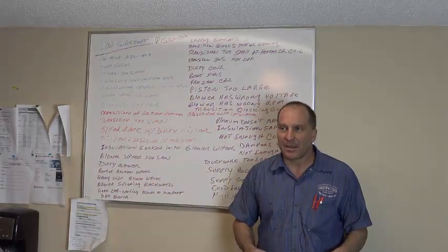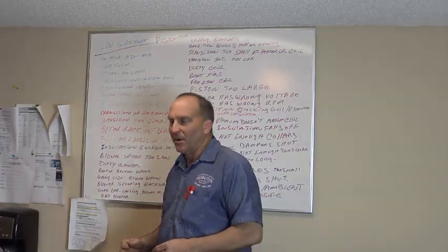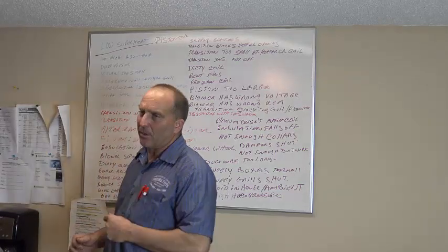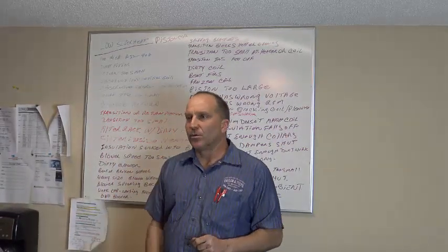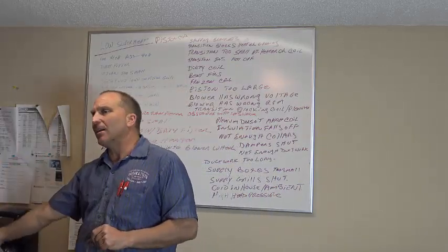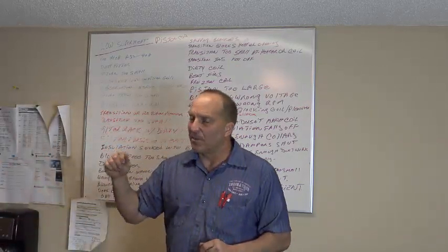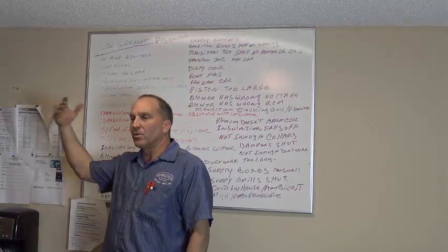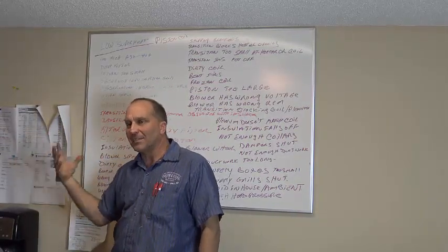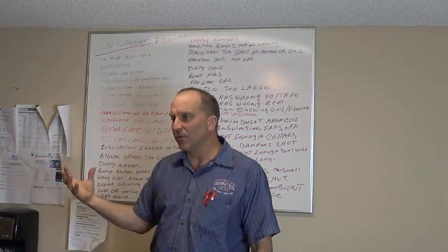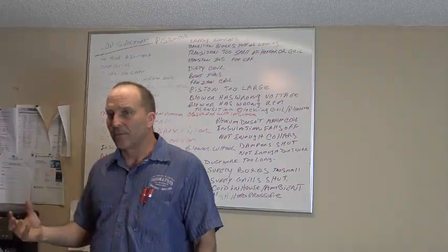If you take a Magnehelic gauge or an inclined manometer and you only check the return static pressure and you come up with that number, and then you go to the supply and you take that number, whatever it comes up with, you may have a 2.0 static pressure inside your supply plenum. That's an extremely high static pressure. That would be an indication of not enough ductwork.